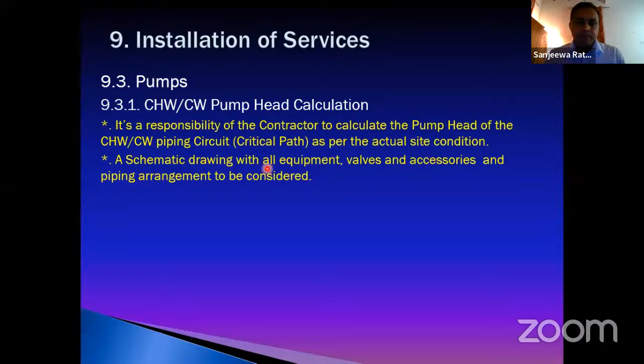Even though pump sizing is done in the tender stage, and the engineer has specified the flow rates and the head, the contractor must verify the values are as per the site situation. Sometimes, for example, if you take the chiller evaporator coil, the pressure drop may change from product to product. So this has to be considered by the contractor. The longest path may vary. So when the installation time comes, it is the responsibility of the contractor to find the critical path and calculate the pump head, and then order with the approval of the consultant. He has to proceed with the procurement.